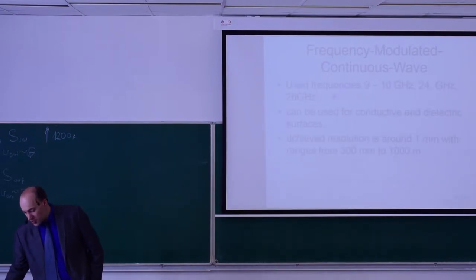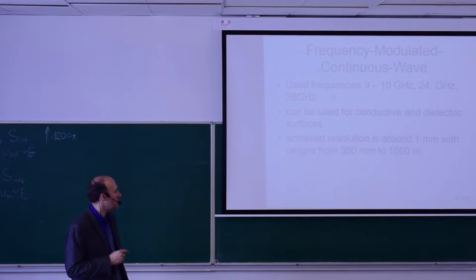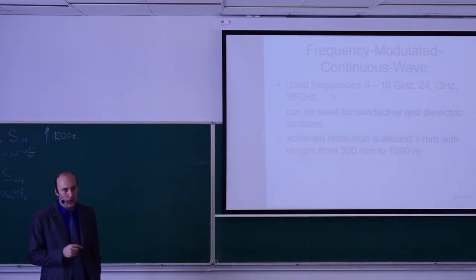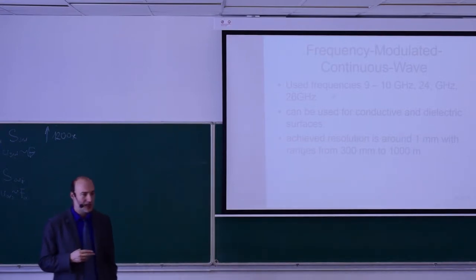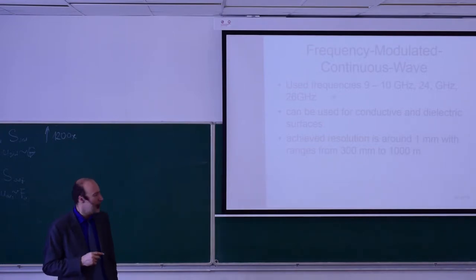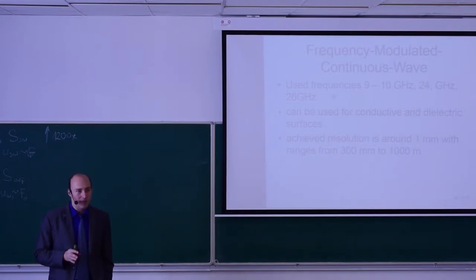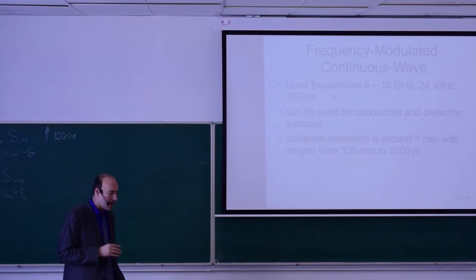The ranges for radar distance meters are roughly between 300 millimeters for frequency modulated continuous wave up to about one kilometer. In industrial systems it is around 10 meters, so industrial liquid level sensors work in a smaller range. The resolution you can expect is approximately one millimeter, so it is quite accurate.